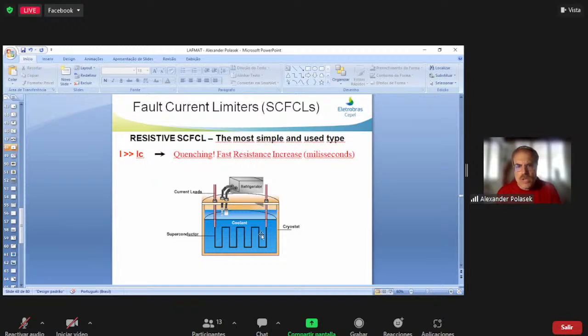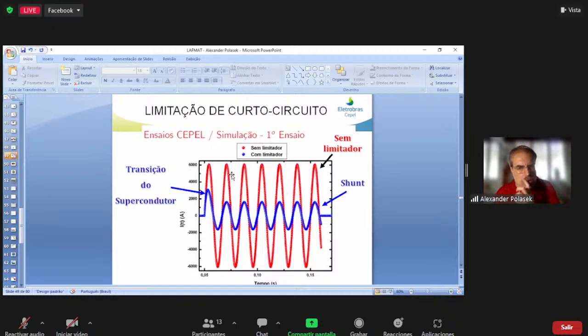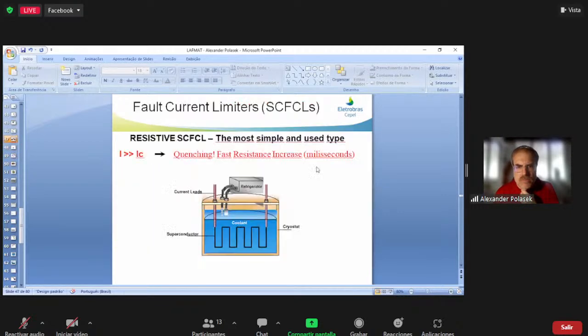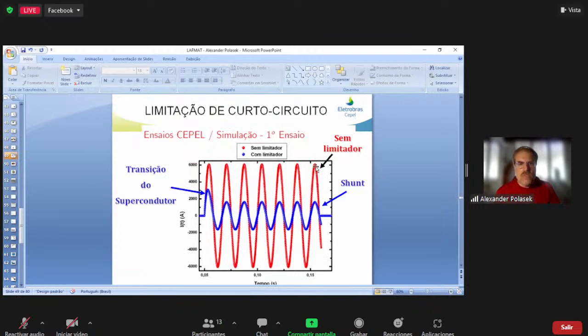And in milliseconds, you have a transition from superconductor to a resistive material. What happens is this. The red curve shows the short circuit without the fault current limiter. In the blue curve, you can see what happens when you have a fault current limiter. And it's very nice because you have a circuit breaker here, but it will protect the circuit breaker, because if the red curve is above the circuit breaker capacity, this will happen. So the idea of fault current limiters is, if the short circuits are increasing in many places, and you don't have to substitute or recapacitate the substation, you can use a fault current limiter.